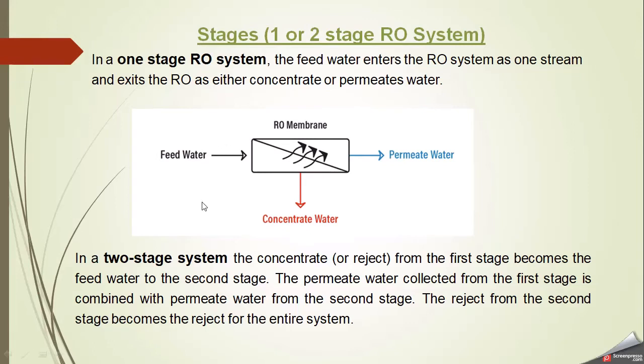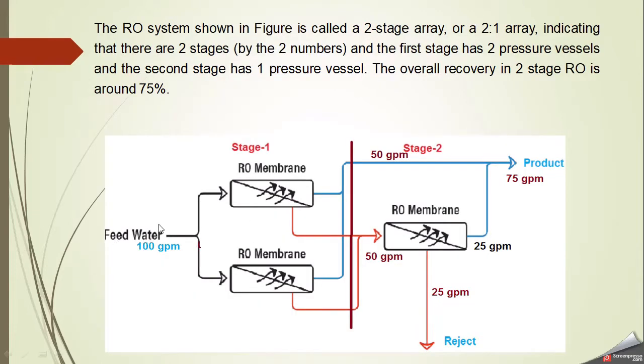In a two-stage system, the concentrate or reject from the first stage becomes the feed water to the second stage. So this concentrate enters another membrane. The permeate collected from the first stage is combined with the permeate from the second stage, and the reject from the second stage becomes the reject for the entire system. You can see in this figure that feed water enters two RO membranes in stage one, the permeate is collected separately, and the concentrate enters another RO membrane called stage two.